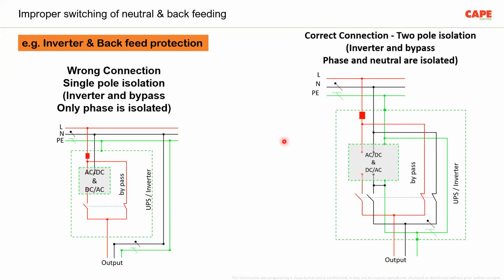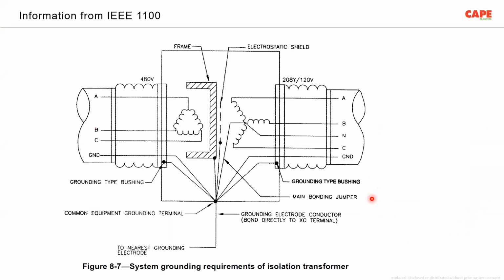So if you are using an inverter, please ensure that you are using this kind of installation, and that the inverter or the UPS is able to isolate both the line and the neutral. Otherwise, this is a reason for accidents. Actually, inverters with single pole switching are a violation of the safety standard. There is a picture in IS 732. We have also made this kind of picture in an upcoming document, so you can probably see it very soon in the National Electrical Code.